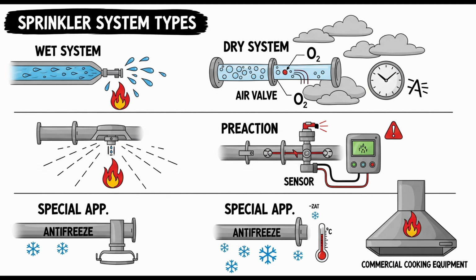What if that pressure gets too high, say, from heat expansion? That's where a relief valve comes in. Wet pipe systems, especially if they have a check valve, like a backflow preventer that stops water from flowing back out, creating a closed loop, basically. Exactly. They can build pressure due to thermal expansion. The water in the pipes gets warmer and expands. NFPA 13 requires a relief valve to handle this.